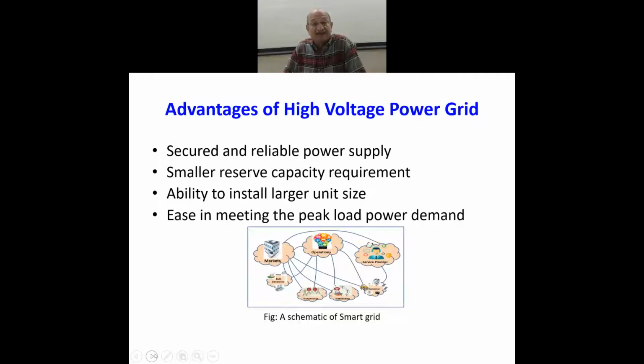So it is desirable to install larger unit sizes, but if a larger unit goes out of the circuit, the whole system gets such a jolt that it may not be able to withstand it with the supply of power to the consumer. But when the total handling capability of the grid increases, we can also install larger units. And that is why the single largest unit should be something between 5 to 10% of the total power handling capability of the system. So that also increases.